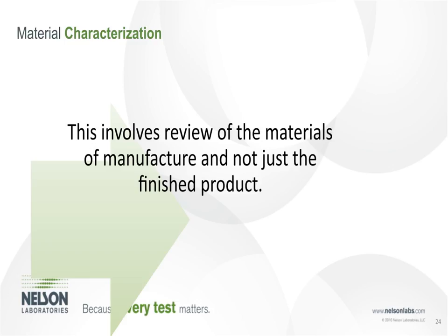But we cannot just evaluate those materials, and this is where a lot of people get in a problem. They get a material from a supplier that may have a master file with the FDA with tons of implant history and data, and they submit that to the FDA and say, we don't have to do biocompatibility, we don't even have to do a safety assessment, because our safety assessment is that this material is safe based off this master file. The FDA will not accept that, because biocompatibility is not just about materials, it's about what you do to them, including sterilization. So please keep that in mind when you're going through a BEP.